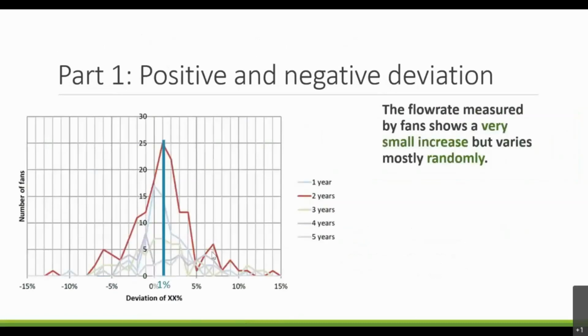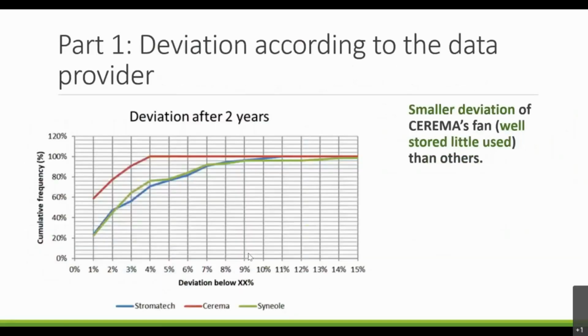We have also plotted the positive and negative deviations, and we found out that the flow rate measured by the fan varies. There is a very small increase of this flow rate, but mostly it varies randomly around zero. Also, we have plotted the deviation according to the data provider, and we found out that the fans from Cerema, who are well stored and little used, deviate much less than other fans. We see that 100% of the fans from Cerema deviate by less than 4%, which is very, very low.